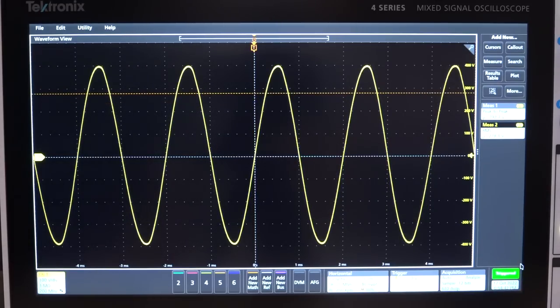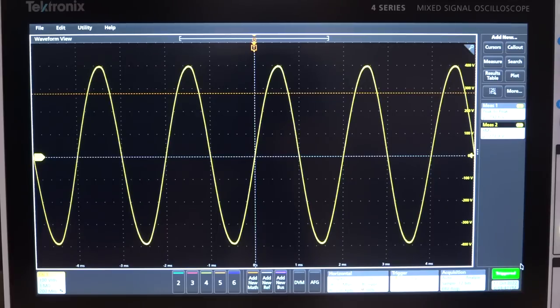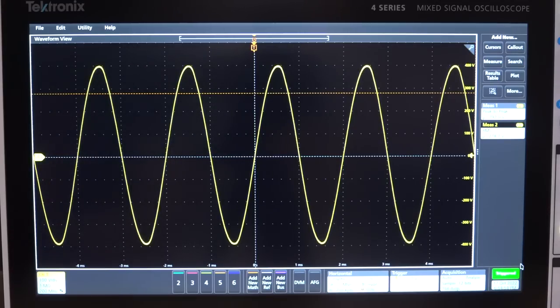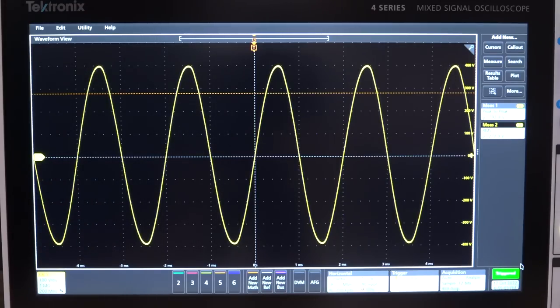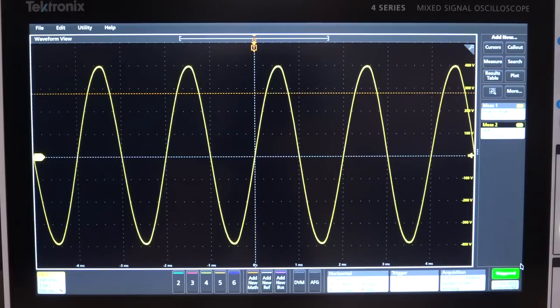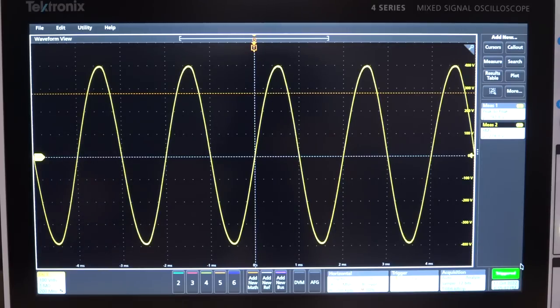The fact that the EEPROM from the 100 model is detecting the correct probe, and remember the attenuations are all different, so if this was still wrong it wouldn't have worked like this. I think everything looks good. I think my conclusion that something on the PCB must be populated in such a way to tell the master controller which model it is is probably the right approach. I hope that you liked this video. Let me know in the comment section what you think about this issue. If you have this similar probe, thanks to Ilya he has the firmware on his website now. The link is in the description. You can also grab it from there. I'll see you next time.